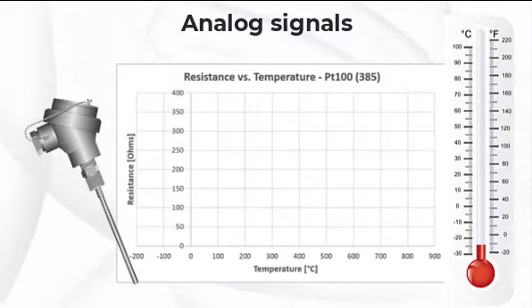The PT100 has a resistance of 100 ohms at 0 degrees Celsius and 138.4 ohms at 100 degrees Celsius. So the resistance changes continuously from 0 degrees to 100 degrees.